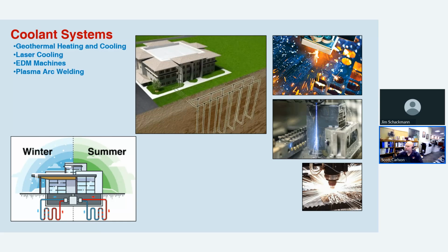You also have situations where you have a piece of equipment that the fluid needs to go right across the head of the cutting tool, especially with plasma and lasers. As they heat up, the width of the cut becomes inconsistent, and it's hard to make parts within tolerance when the temperature isn't controlled. So you can use a regenerative turbine pump to push fluid directly across the cutting tool. That gives it the ability to stay cool and consistent the entire time it's in operation.